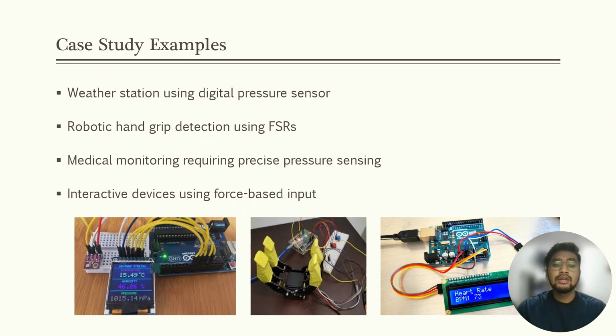There are case studies that have been done using digital pressure sensors and FSRs. For example, in a medical ventilator, pressure must be monitored continuously and accurately. In this case, the digital pressure sensor is clearly the better choice because accuracy and reliability are critical.